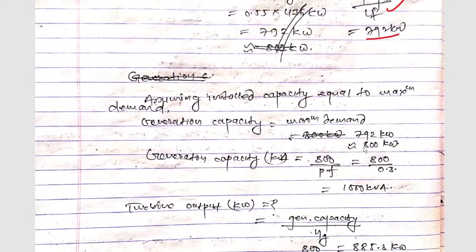Now maximum demand will be average power upon load factor also. So if you calculate we'll get here 792 kilowatt. Now assuming installed capacity equal to the maximum demand, so generation capacity will be the maximum demand and we have the maximum demand as 792 and that is equivalent to 800 kilowatt.